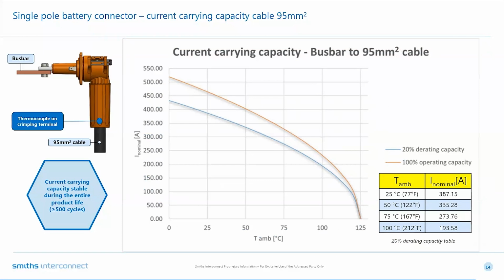In this slide is presented the same test results, but for the 400 amps connector size, crimped on a 95 square millimeter cable. And as said before, the current carrying capacity remains stable during all the product life, with a nominal current value greater than 380 amps at the standard ambient temperature and greater than 270 amps at an ambient temperature of 75 Celsius degree. As before, this connector size can also be equipped with a 4x0 AWG size or a 120 square millimeter cable, increasing the current carrying capacity.